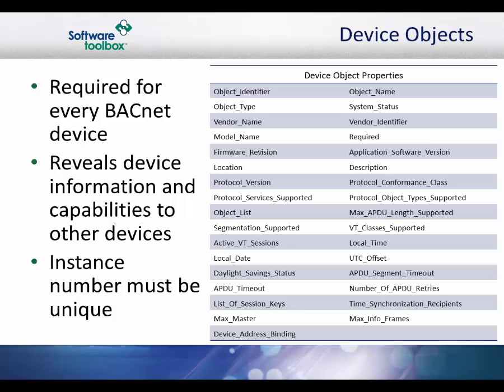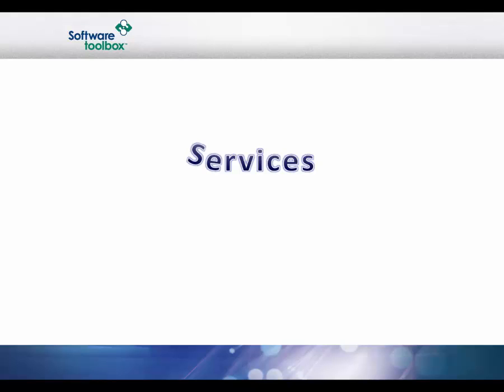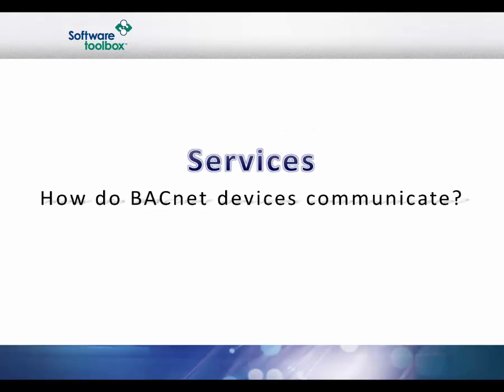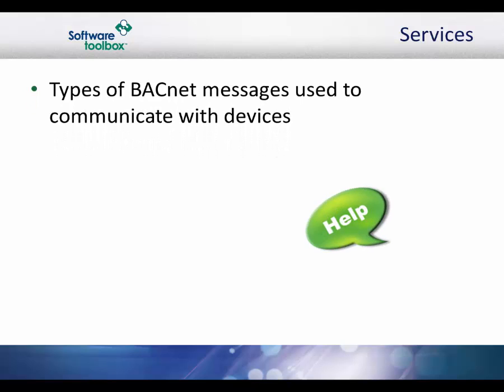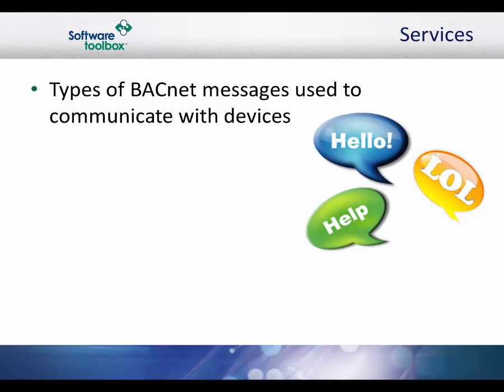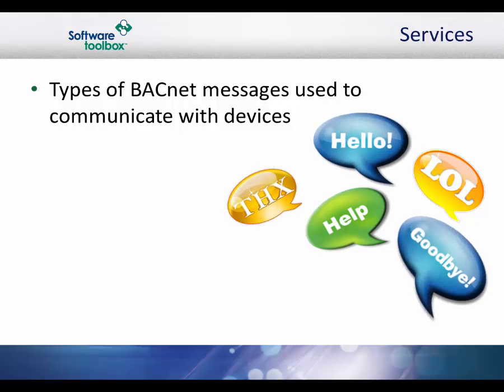It may also be used to conveniently identify the BACnet device from other devices during installation. Because BACnet is based on a client-server model, BACnet messages are called service requests. The BACnet protocol defines a number of services that are used to communicate between building devices. The protocol services include Who-Is, I-Am, Who-Has, and I-Have, which are used for device and object discovery. Services such as read property and write property are used for data sharing. A client machine sends a service request to a server machine, which then performs the service and reports the results to the client.